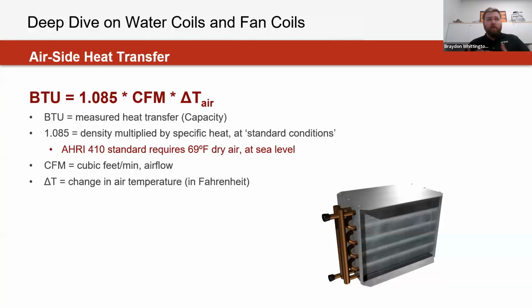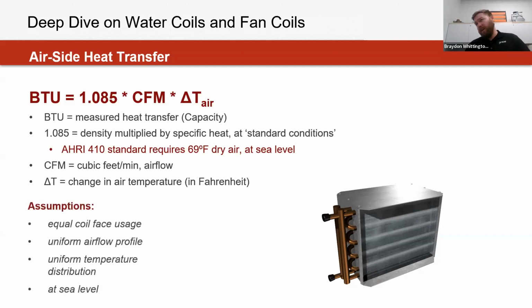So one of the most common ways that we see calculating, or the initial step of calculating, heat transfer for water coils is through this airside heat transfer equation. Simple, effective, to be able to determine how much MBH is going to be coming from a coil, essentially evaluating based off the temperature rise of the entering air conditions going through these coils at a certain CFM, how much capacity or BTUs is going to be coming from it. One thing that we'll really notice there though is the 1.085, which essentially is a constant.